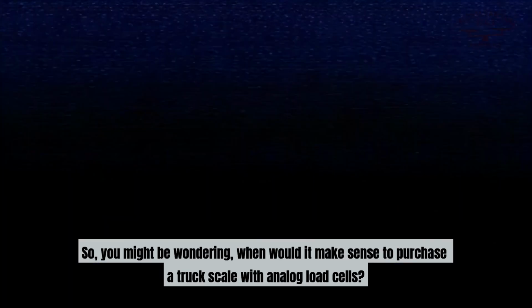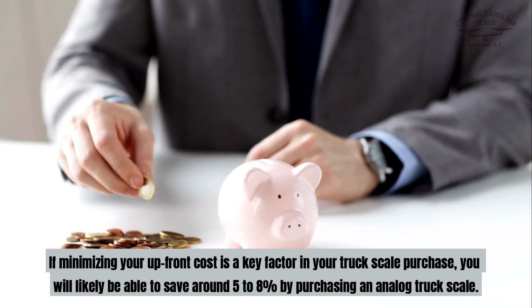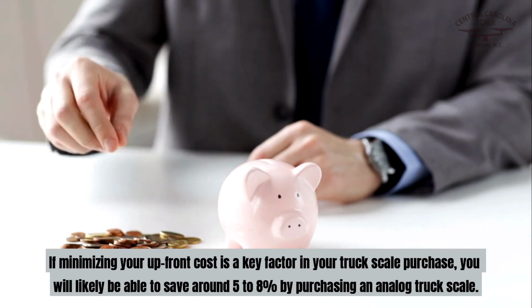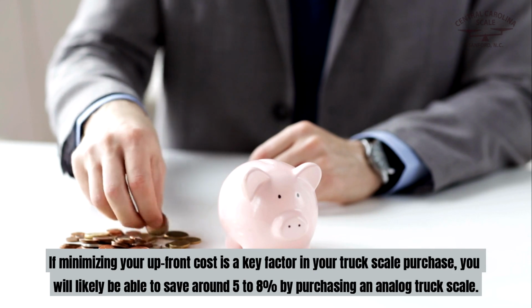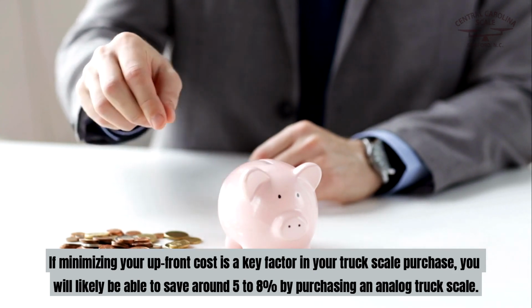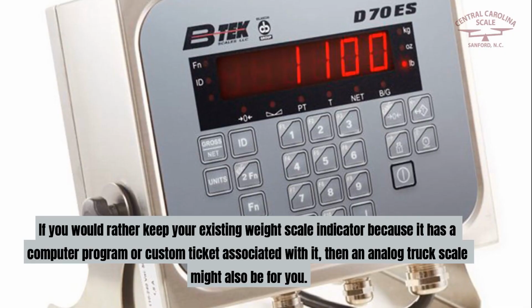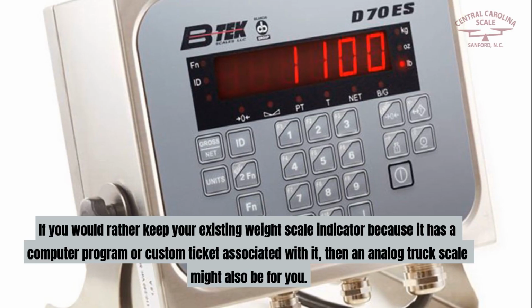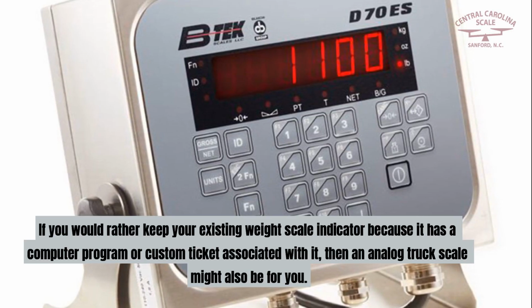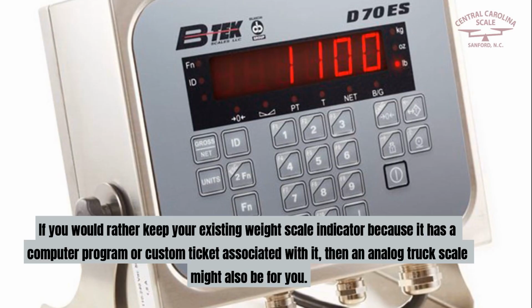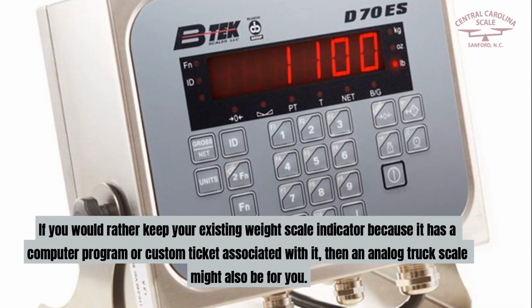So you might be wondering, when would it make sense to purchase a truck scale with analog load cells? If minimizing your upfront cost is a key factor in your truck scale purchase, you will likely be able to save around 5 to 8% by purchasing an analog truck scale. If you would rather keep your existing weight scale indicator because it has a computer program or custom ticket associated with it, then an analog truck scale might also be for you.